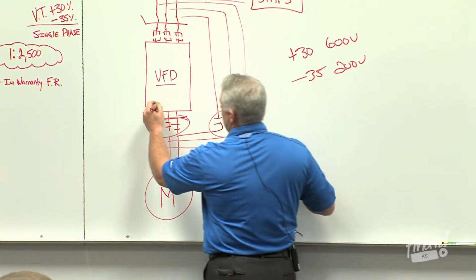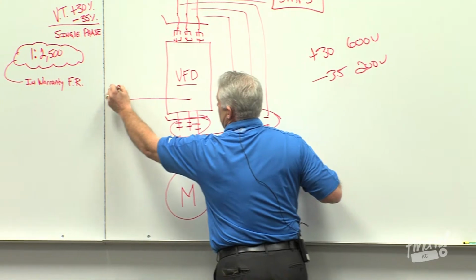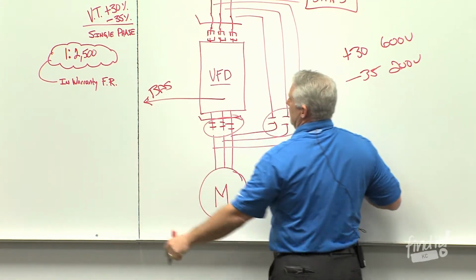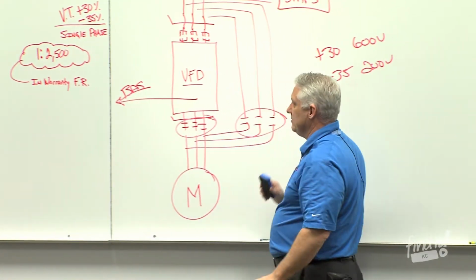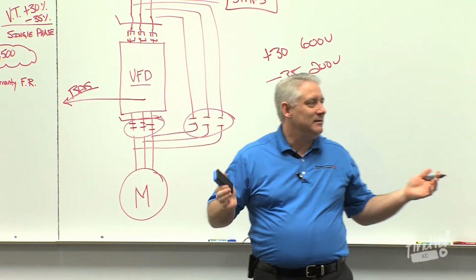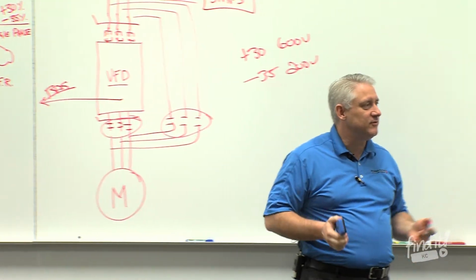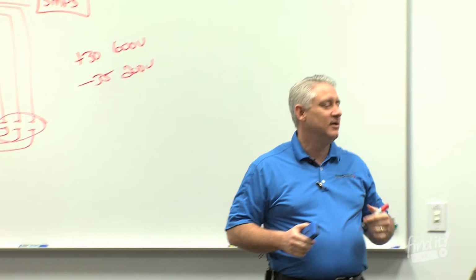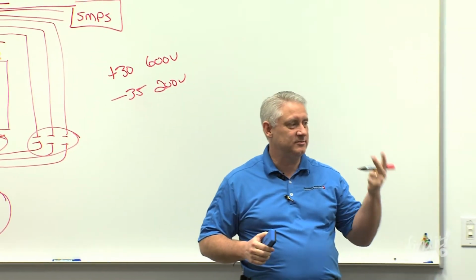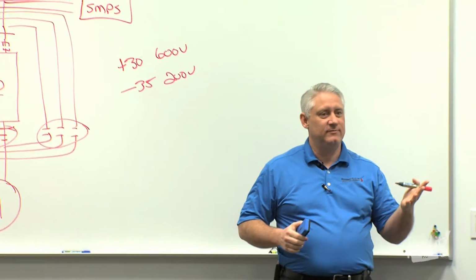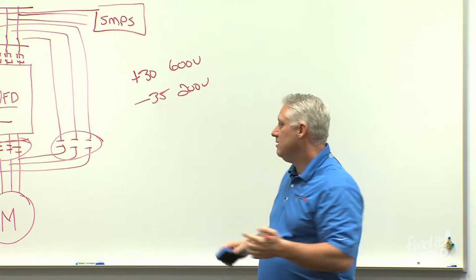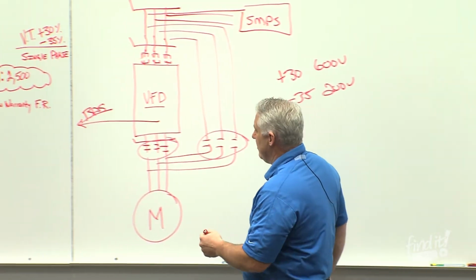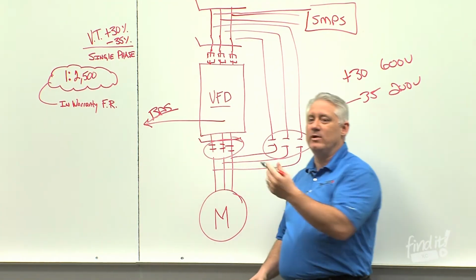And VFDs for a long time have communicated back out to the building automation system. I mean, they just have for many, many years. Probably early 90s was the first Siemens system we put in. ABB was the first with Siemens, first with BACnet, first with Johnson, first with Modbus capabilities. So what we've done now is we've added all those capabilities to the bypass as well.